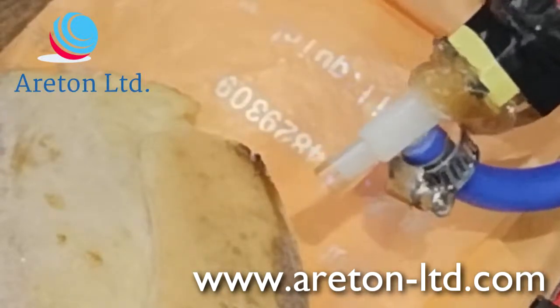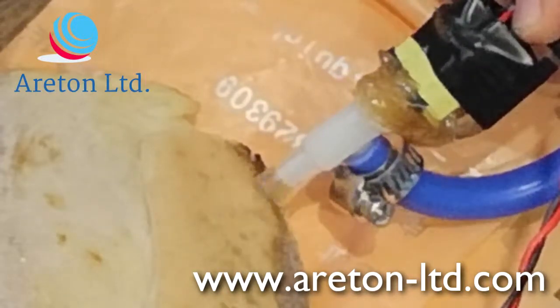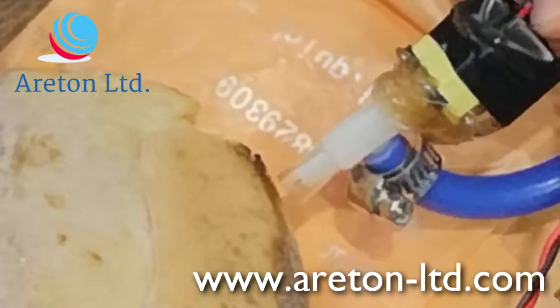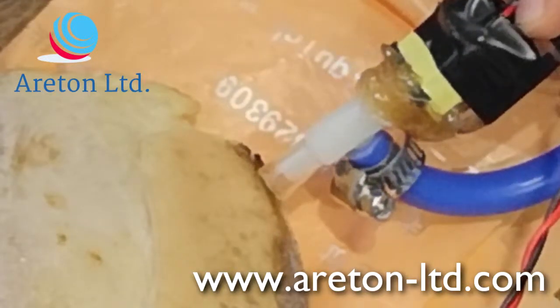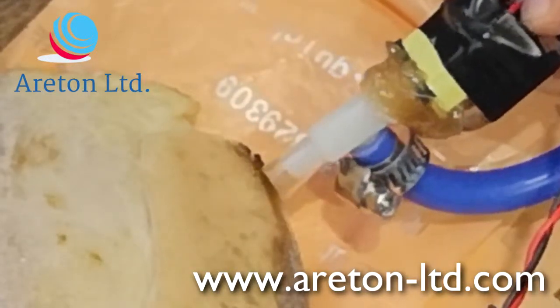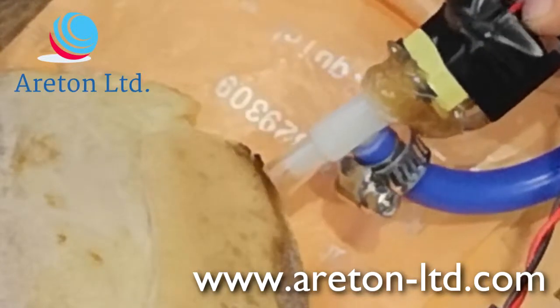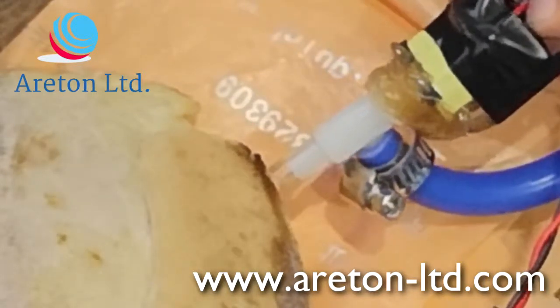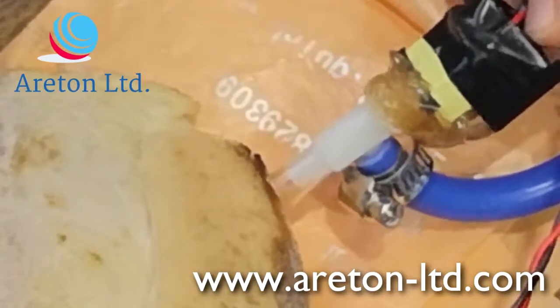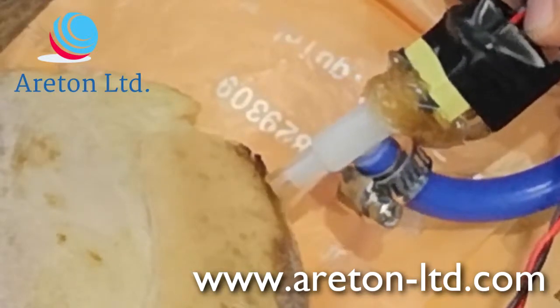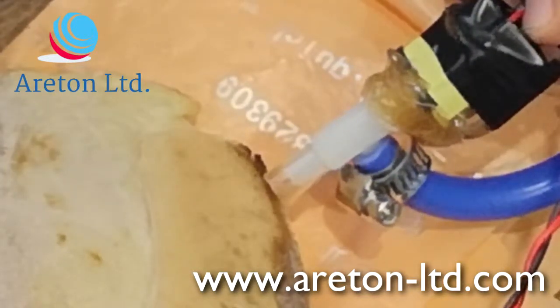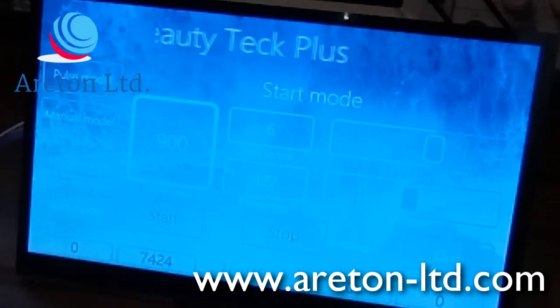So now it's off. After 6 seconds, it's going to come on again. Look. And it's off. What has happened there is that it had been on for a while longer, simply because it hadn't detected the arc being on, because of the setting of the device. That's something that we're going to sort out later on, but that gives you the idea.